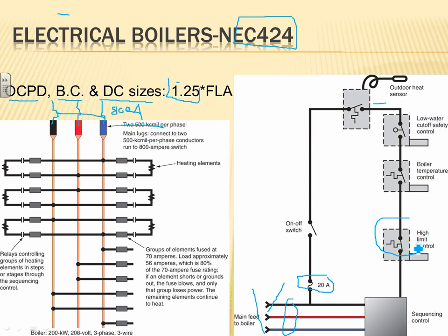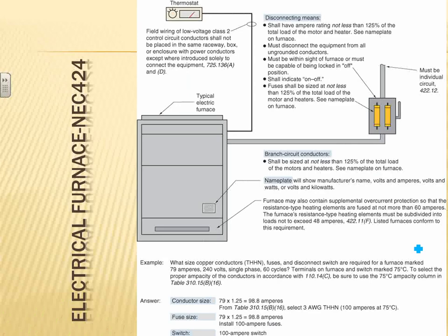That's the heat in your HVAC system. Here's a good example of that particular heater disconnect. I threw this one directly for you. It's an electric furnace. I want to bring to your attention, guys, that when you have heat and cool, you're dealing with a class 2 circuit, and class 2 circuit is always Article 440, 725. And all the stuff that we just talked about from the nameplate is sized right in here. So in this case, I have a 100 amp fuse, disconnect, and conductor.